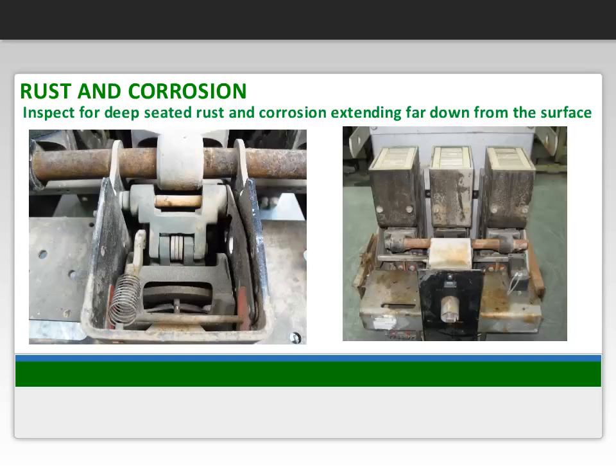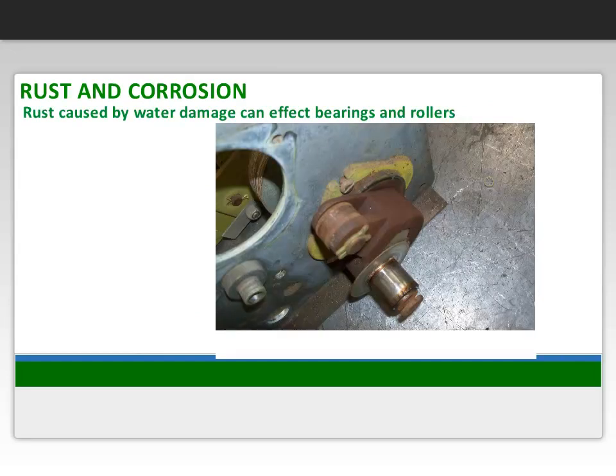What we're looking for is deep-seated rust and corrosion like you see in this mechanism. This could be a sign of water, salt, or chemical damage which can severely impact the opening and closing operation and speed of this unit. A unit like this would require replacement parts and a total disassembly and rebuilding, probably not cost effective to rebuild and obviously not a candidate for inspection and test. As you can see in this image, the roller bearing assembly is badly showing signs of rust. Always replace bearings and rollers covered with surface rust that have any pitting. Particles may be introduced into the rollers and interfere with the ability to form a proper fluid wedge.